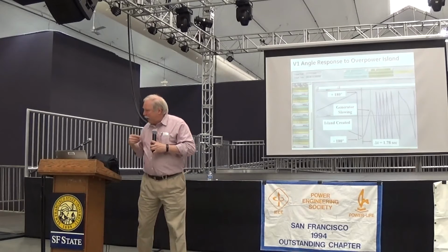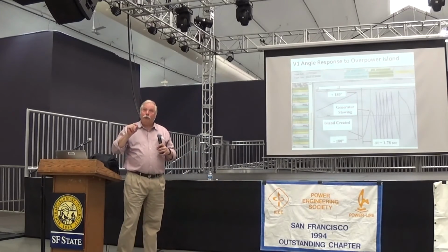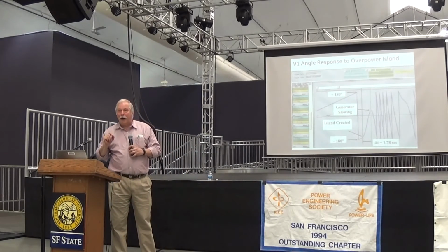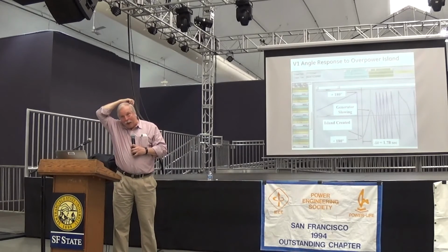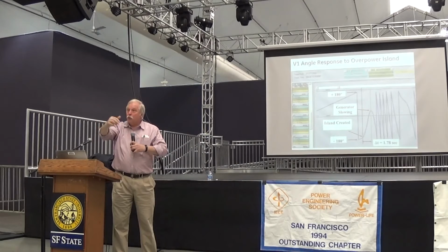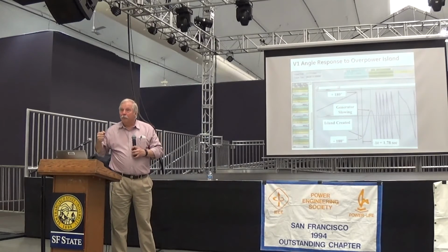And what you're looking at here is the synchrophasor angle response of an unbalanced island. So when we separated from the main utility with 10 megawatts of excess generation.